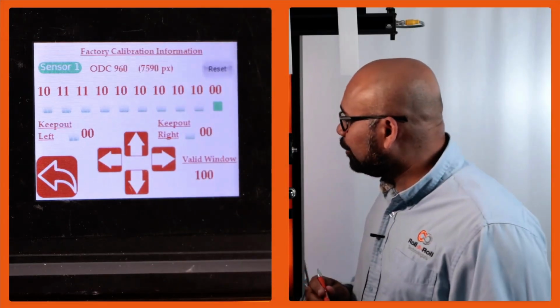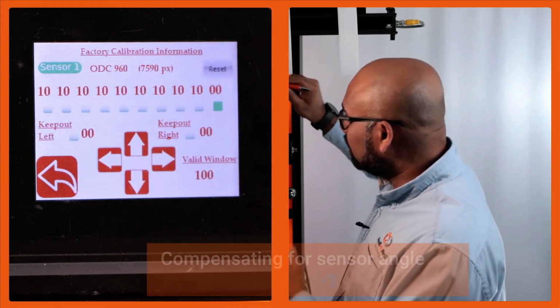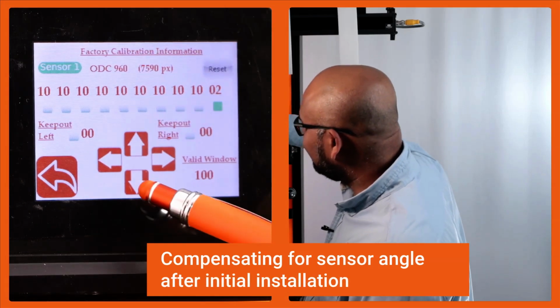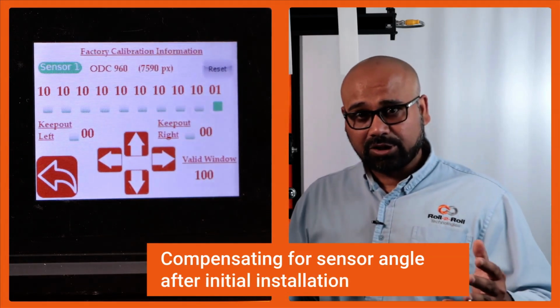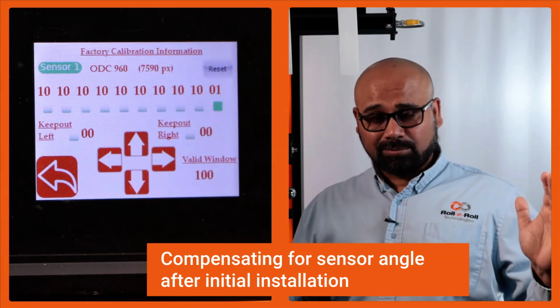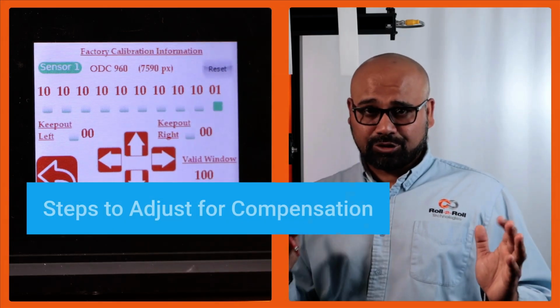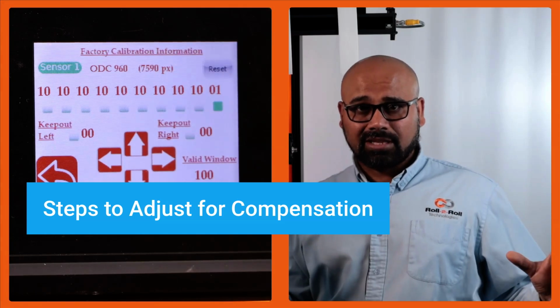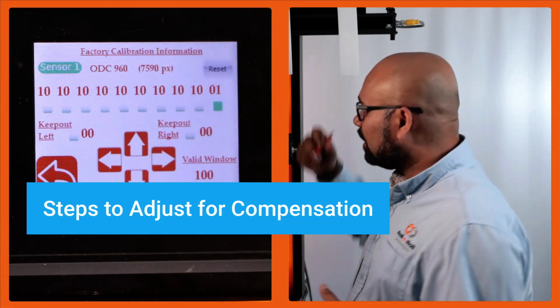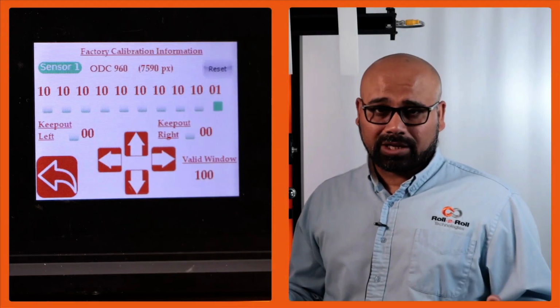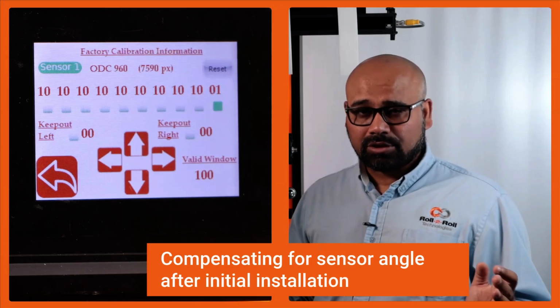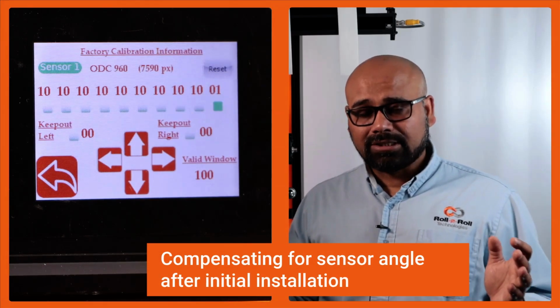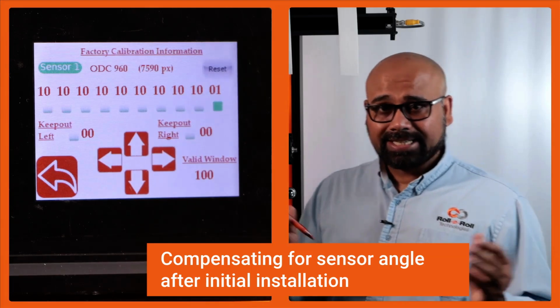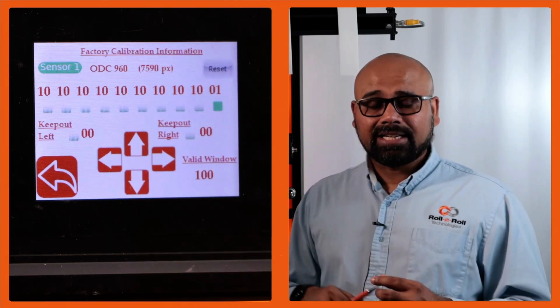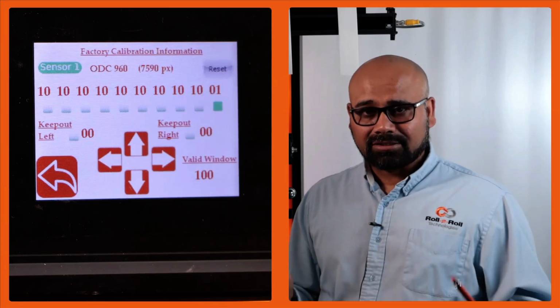The second thing we need to do is compensate for the angle. We have documentation that you can look at, and it will tell you what that number means. There's a small measurement that you need to make when you do the first installation. Once you have that number, you come in and enter it in that last column. These two things are necessary if you're looking for a measurement resolution of sub-millimeter, actually sub 250 micron. Anytime you want that high a resolution, we need to make sure we have these things set up.